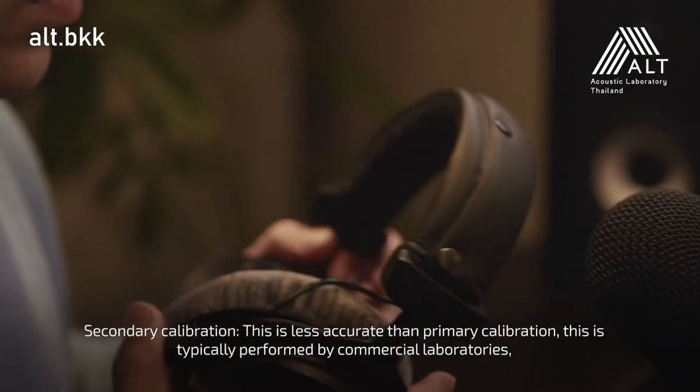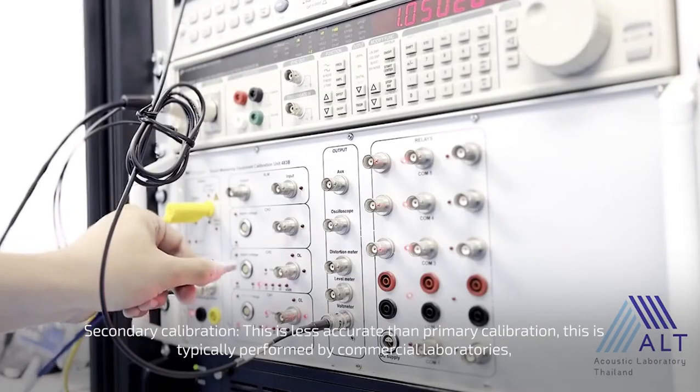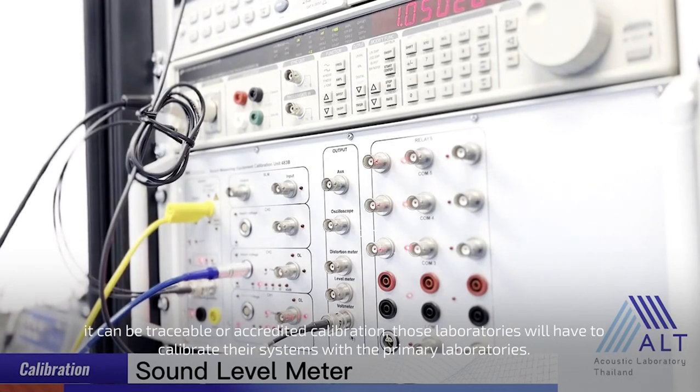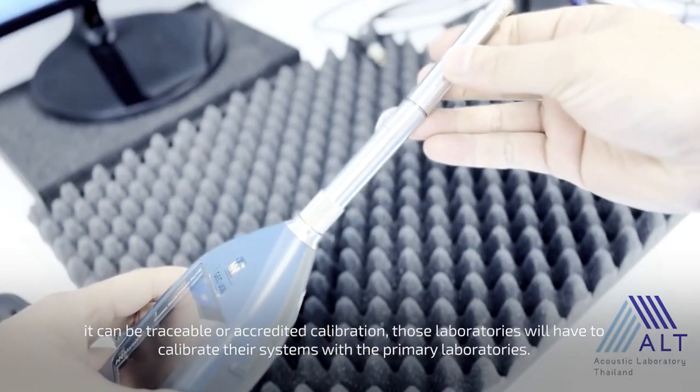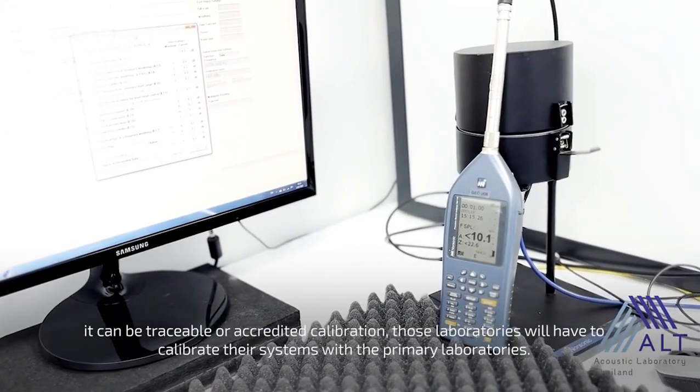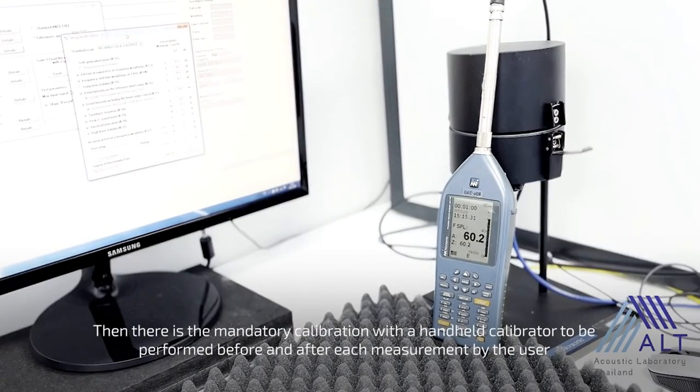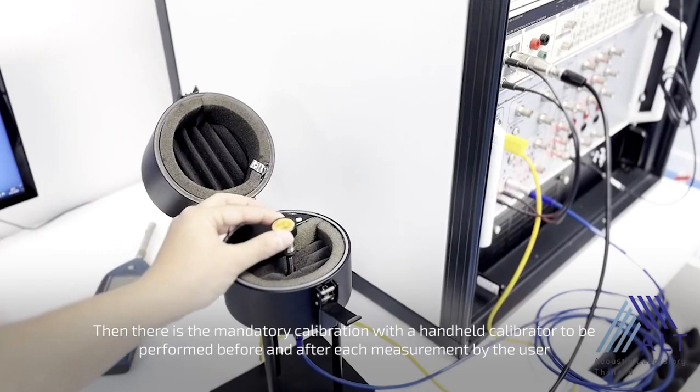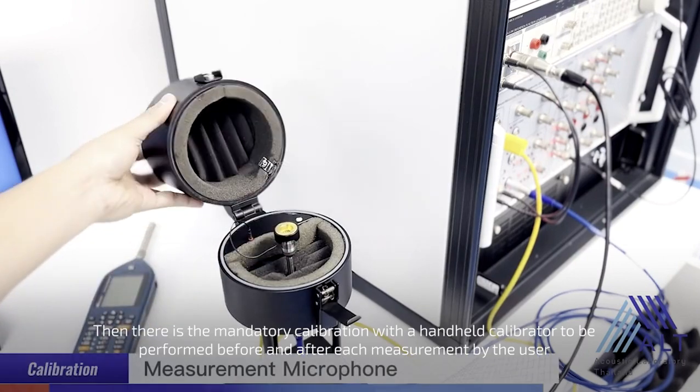Secondary calibration is typically performed by commercial laboratories. It can be traceable or accredited calibration. Those laboratories will have to calibrate their systems with the primary laboratories. Then there is mandatory calibration with a handheld calibrator to be performed before and after each measurement by the user.